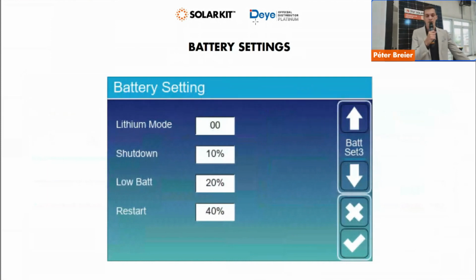On the third page, you will see 3 percentages in lithium mode. Lithium mode is set to 0 automatically. It's for the compatible batteries and Deye's own batteries as well, so you don't need to change that. If, for some reason, it's not on 0, then please set it to 0, but I never encountered a situation where this was changed originally.